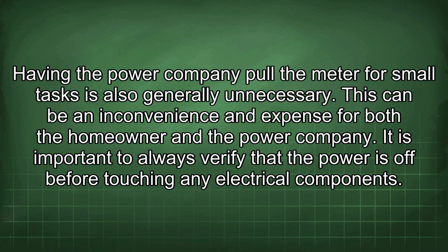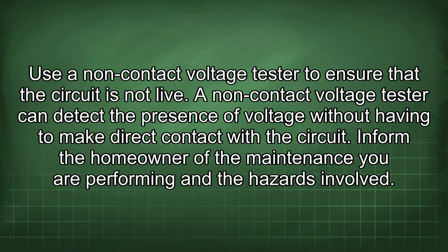It is important to always verify that the power is off before touching any electrical components. Use a non-contact voltage tester to ensure that the circuit is not live. A non-contact voltage tester can detect the presence of voltage without having to make direct contact with the circuit.